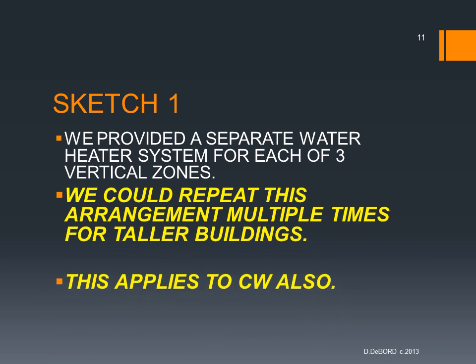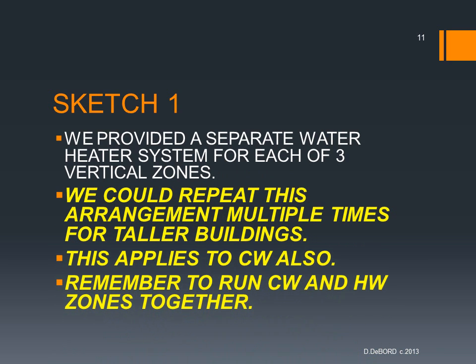So we provided a separate water heater for each of the zones. Now we could take the same system with the 3 zones and we could repeat this arrangement multiple times for taller buildings. Could we go beyond 3 zones? Yes, we could. And remember, because we're not upfeeding, we have some extra latitude there. But then, however many zones we have, we can multiply that going up the building to build a system for whatever height we need.